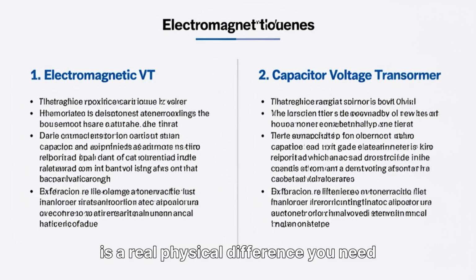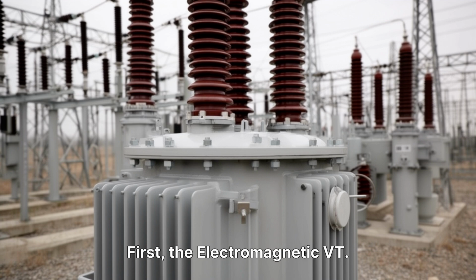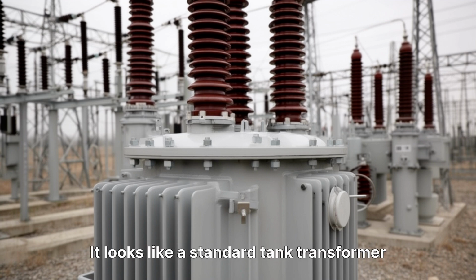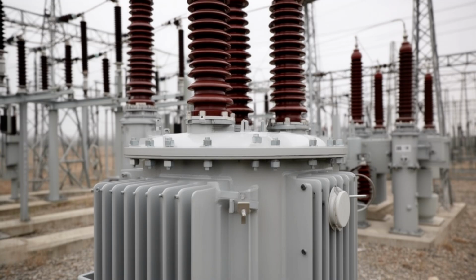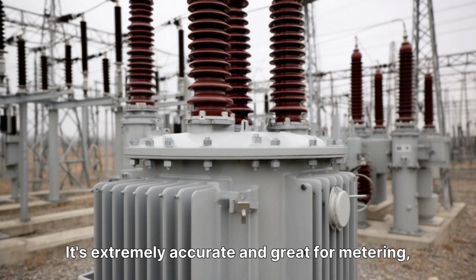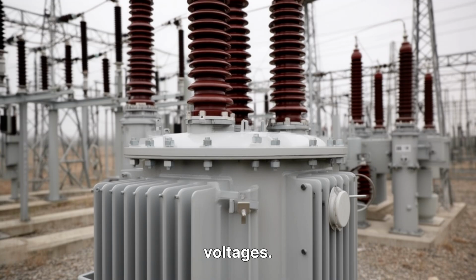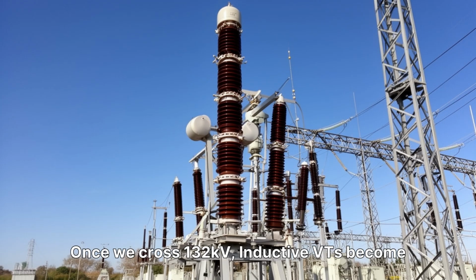While VT versus PT is just a name change, there is a real physical difference you need to know. Inductive versus capacitive. First, the electromagnetic VT. This is the old reliable. It looks like a standard tank transformer with a big iron core. It's extremely accurate and great for metering, but becomes expensive and heavy at high voltages. Once we cross 132 kV, inductive VTs become too expensive.